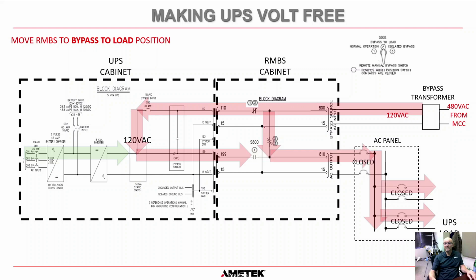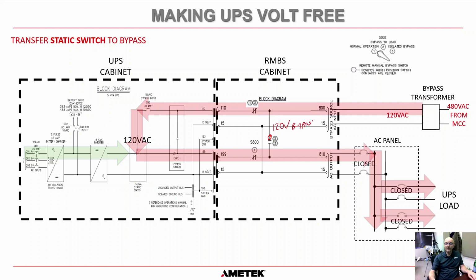Because the next thing we're going to do is move to position 2. And what that does is it closes this contact here. And let me go back to the previous page. Okay, so you can see on this side of the contact here, we're going to have the 120 volts AC from the bypass. Okay, and if you follow that, that also goes all the way down here. So on this side of the switch, you're also going to have 120 volts from the bypass. So it is the exact same voltage, phase relationship, frequency, everything is identical because it is the same power source.